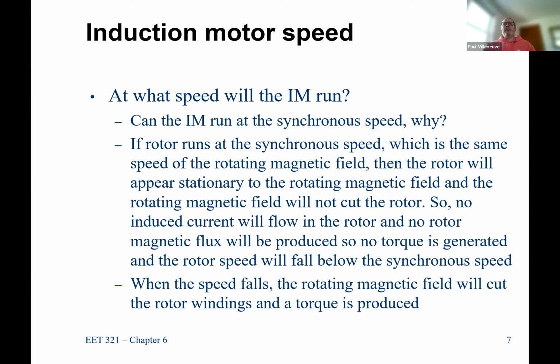No relative changing magnetic field means no current flow is induced, because you don't see a changing magnetic field. And once you get to 1800 RPM, the current goes away and then the speed starts to drop. Once the speed starts to drop, you get a current flow, it increases back up, and then you get it operating that way. All right, does that make sense? Pretty important characteristic to understand.